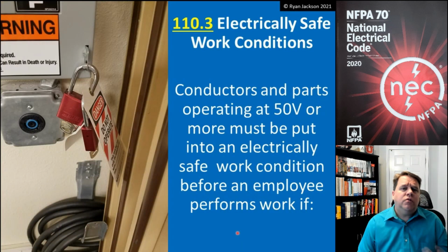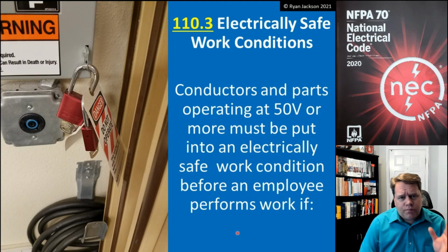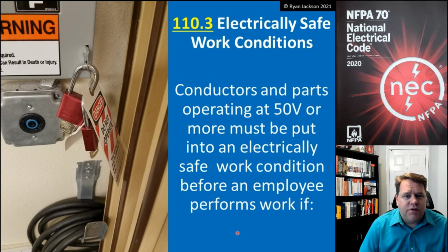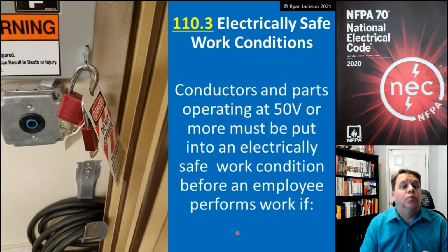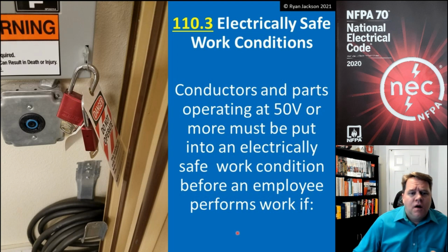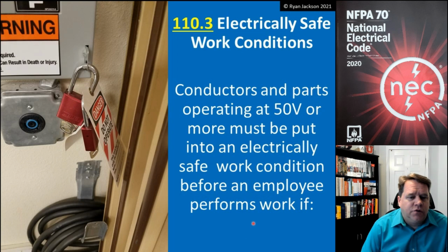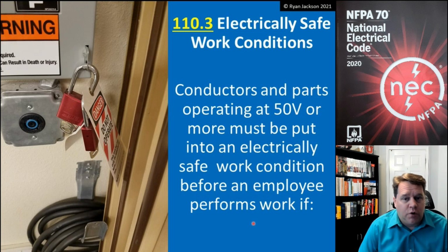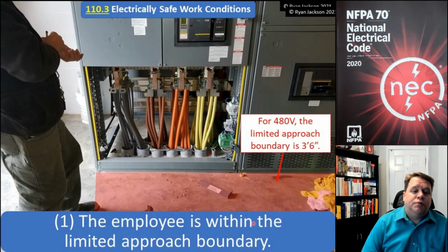So how do we eliminate the hazard? Well, we create what's called an electrically safe work condition. So 110.3 tells us when we need to have an electrically safe work condition. And I know we haven't defined what that is yet, but please bear with me and know that we will define it very soon. So conductors or parts operating at 50 volts or more must be put into an electrically safe work condition before an employee performs work if the employee is within the limited approach boundary.